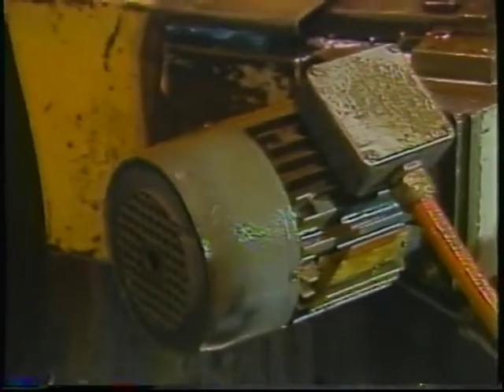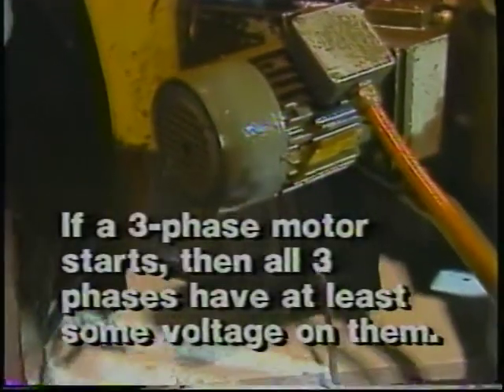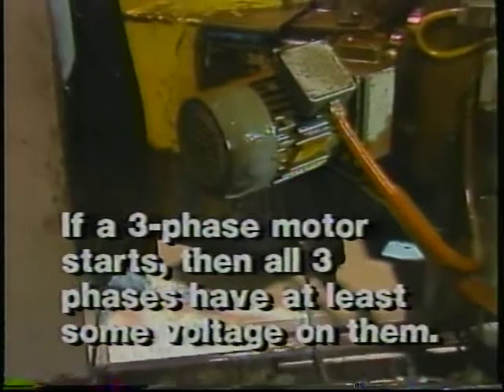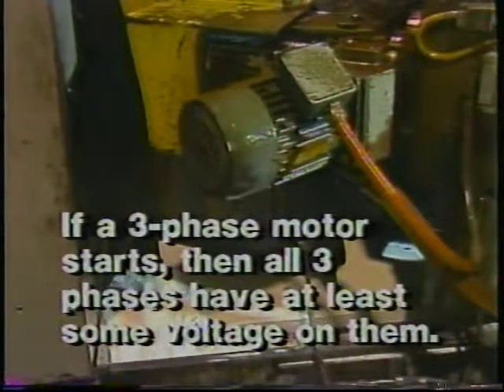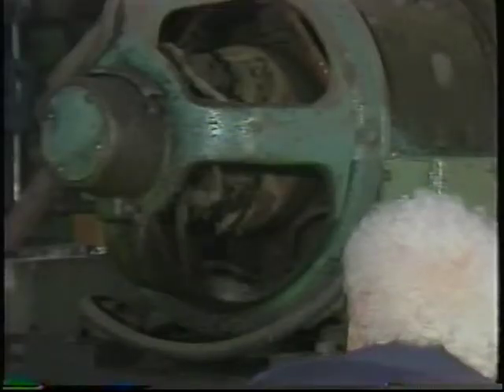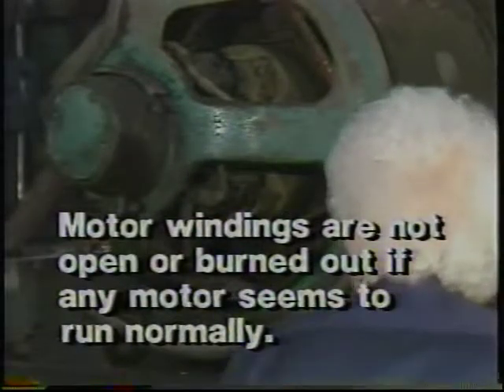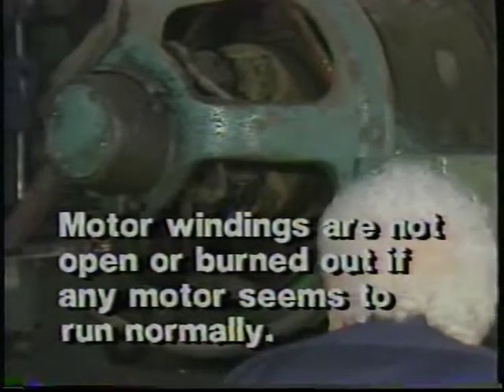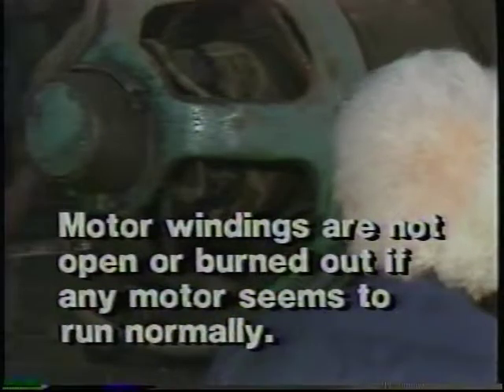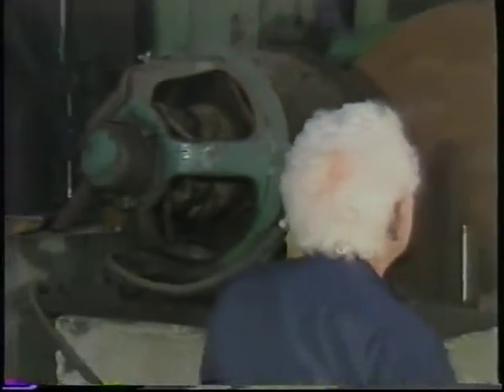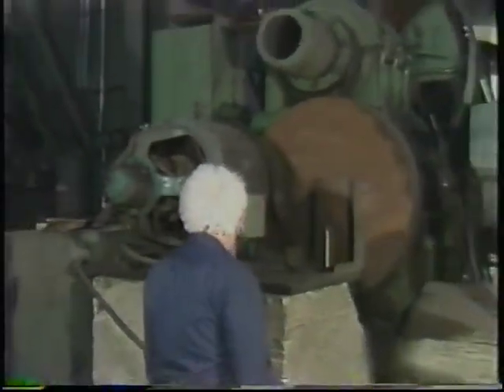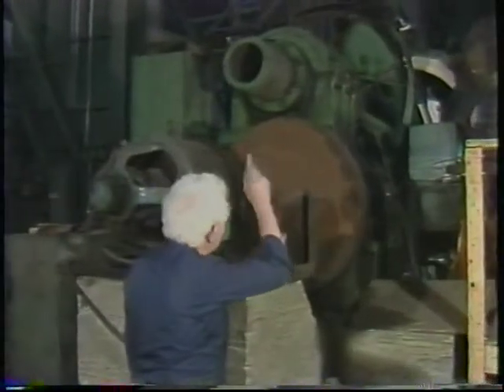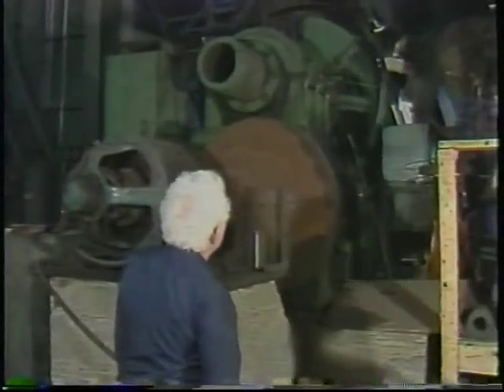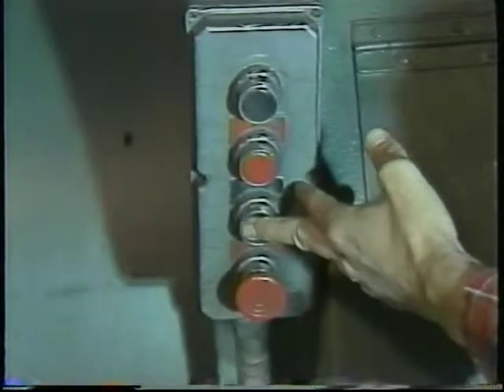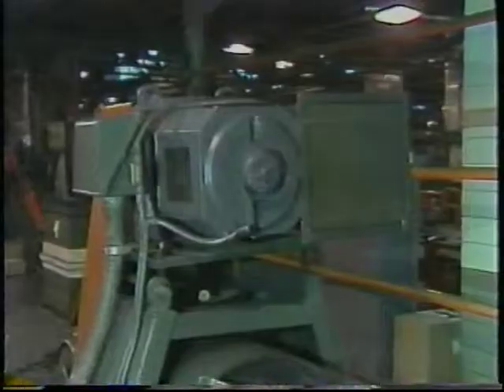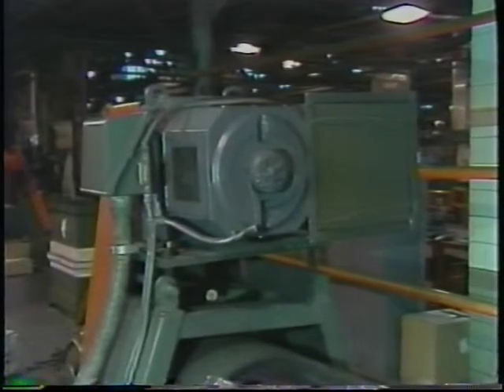If it is a three-phase motor, you know that all three phases have at least some voltage on them, and any fuses in the lines are good. You know that the motor windings are not open or burned out, if any type of motor seems to run normally. It is possible in that case that you do not really have a problem at all. Maybe there was a one-time condition that caused the motor to draw too much current. But if the motor has been tripping its overloads frequently, you will need to track the trouble down.